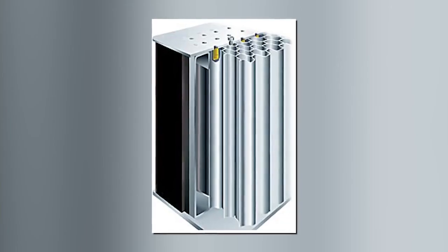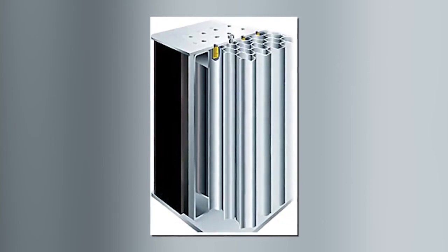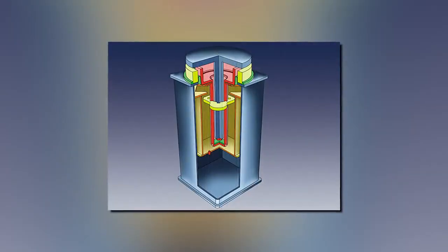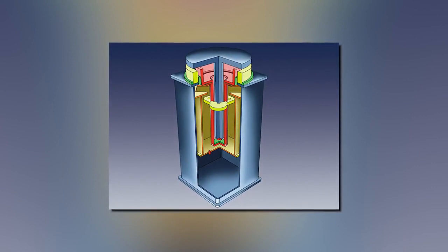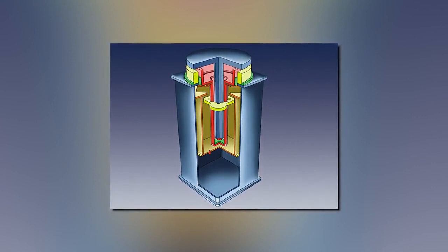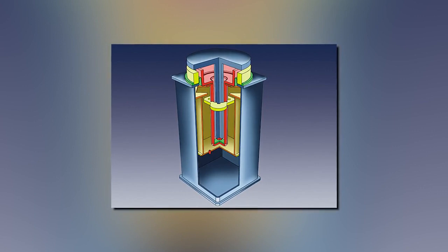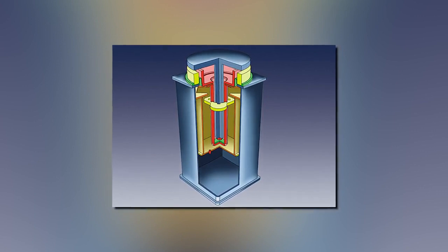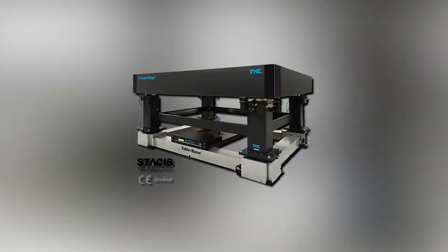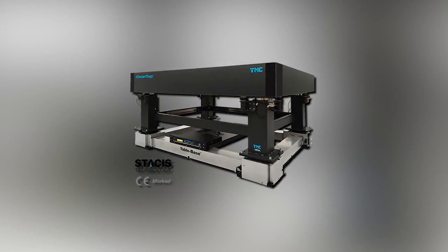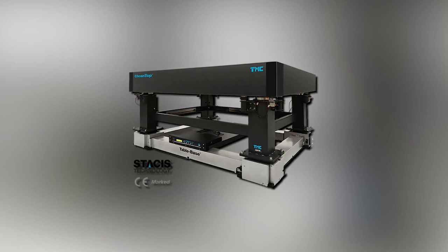If the floor has higher frequency vibration, then we can supply a honeycomb optical top, which is essentially a metallic version of the carpenter's torsion box. Along with that, we can supply our gimbal piston air isolators. The air isolators work as a soft spring with resonance frequency of 2 Hz. It provides isolation above this resonance frequency. If high and low frequency are an issue, then our laser table base could be considered, as it mixes our STACIS and gimbal piston technologies to provide both high and low frequency isolation.